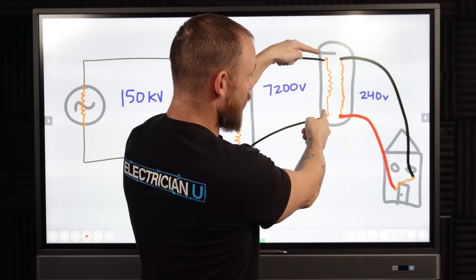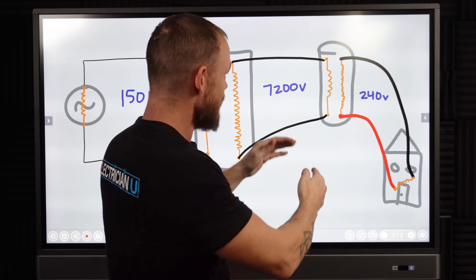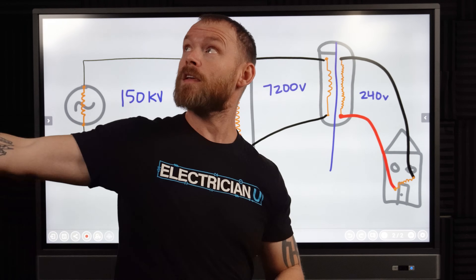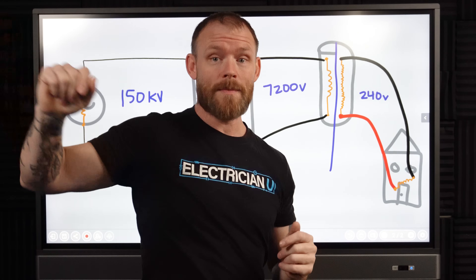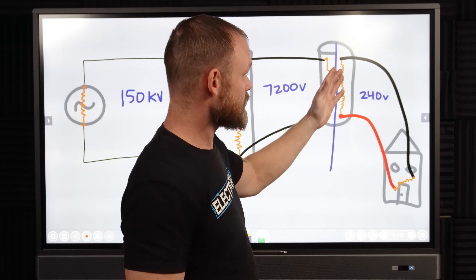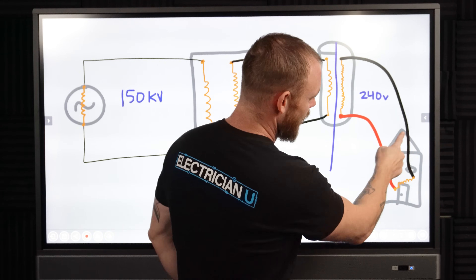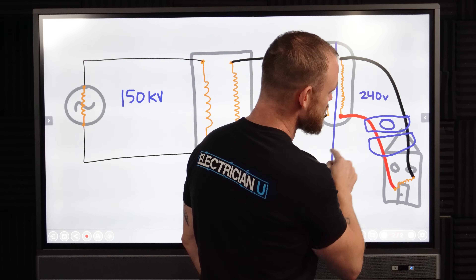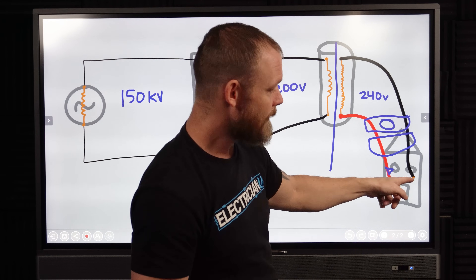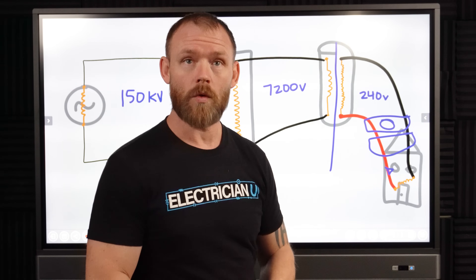All of that is distribution voltage on the primary side of the transformer — that's what we call primary in the field: the entire distribution circuit on the primary side going back to the utility. All the incoming lines you see flying overhead, that's primary. From there, coming down to a house or building is what we call secondary. Secondary power is usually distributed down to about 240 volts, and conductors run down into a house with a panel and a meter in between, connecting to loads like fans, heating elements, or light bulbs.